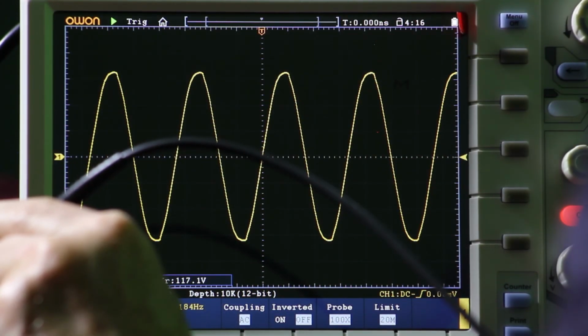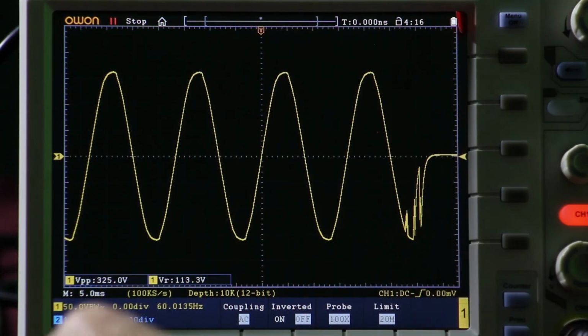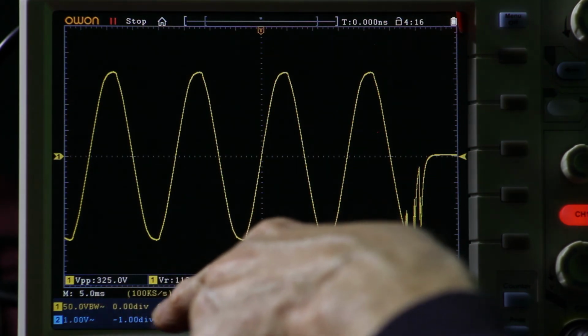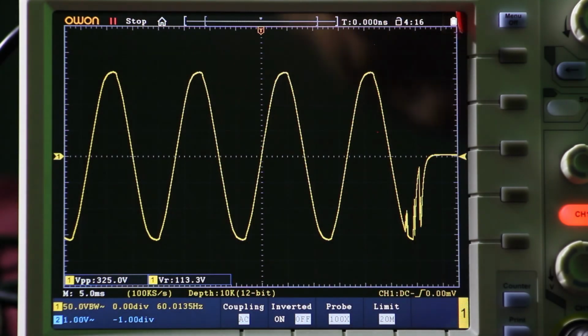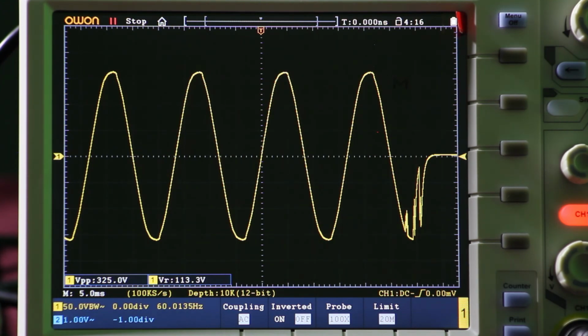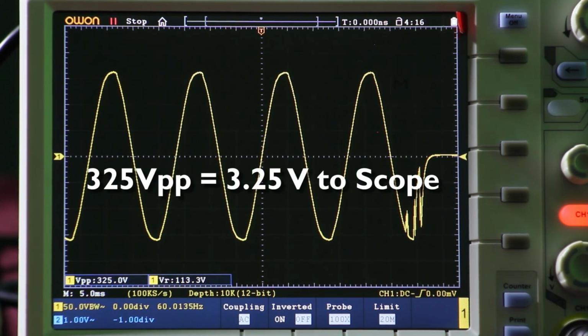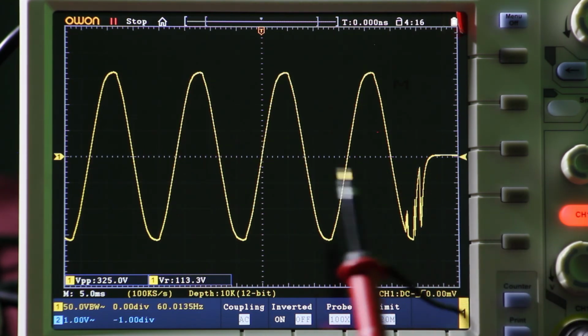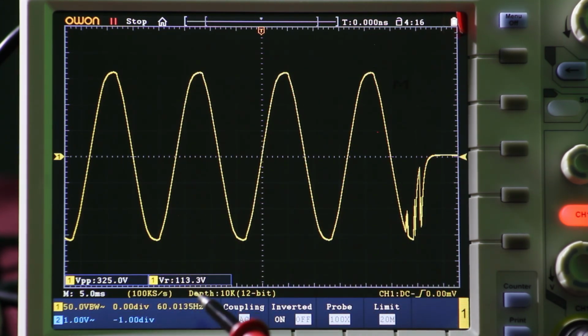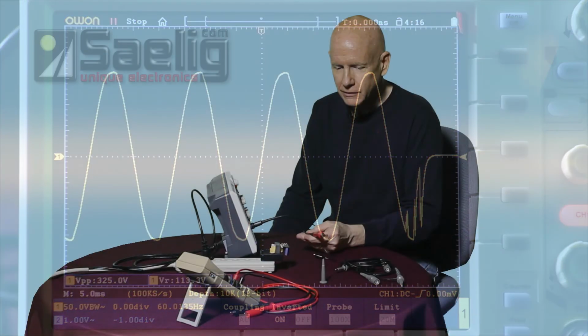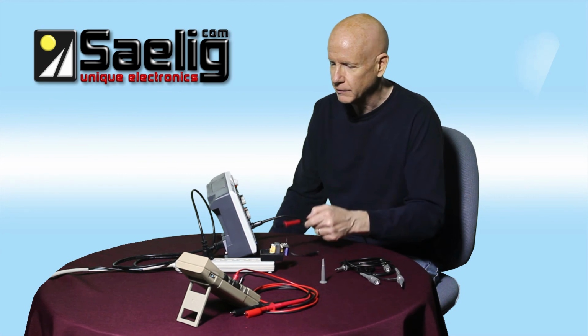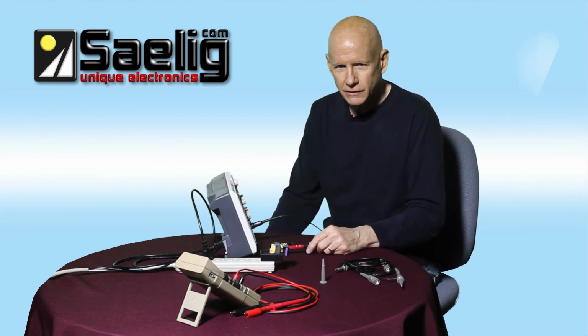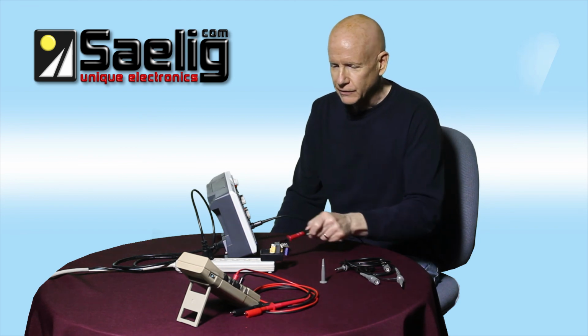Okay, let's just stop that. Now, at any rate, we were able to see again about 325 volts peak to peak, 113 volts RMS, frequency 60.01 hertz. The interesting thing to note is that if this is 325 volts peak to peak, then the voltage being input to the scope is only 3.25 volts. So that's increased the capacity of the scope. It's increased the safety of the measurement quite a bit. And the only thing that we can do to become any more safe on this is to operate the scope on battery or to use a differential probe if you're not sure exactly of what you're dealing with here.